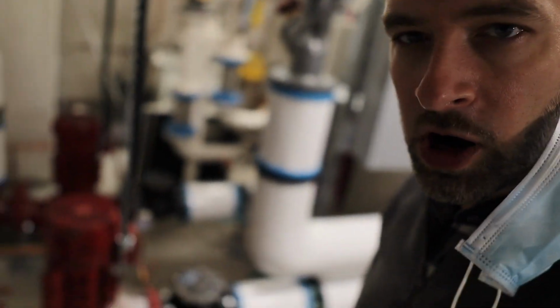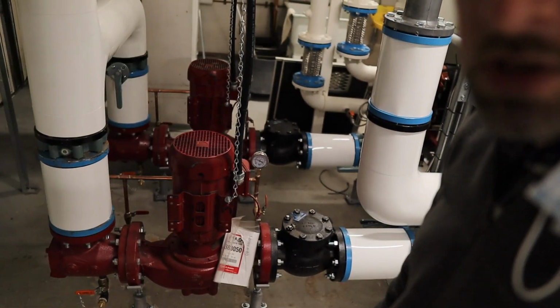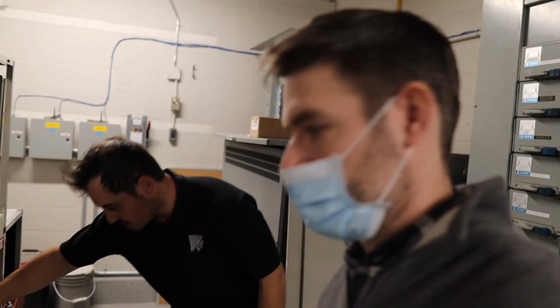So we're just getting ready to start these up. You can see down here we have our pumps into the chillers. Everything's all set up and running. The key here though is to get enough of a load on the building when you're starting it up to get a good run cycle out of this equipment. So that's what we're working on right now, just getting that load up, and they'll be ready to start this up shortly. Allows you to have a heat exchange inside of the...